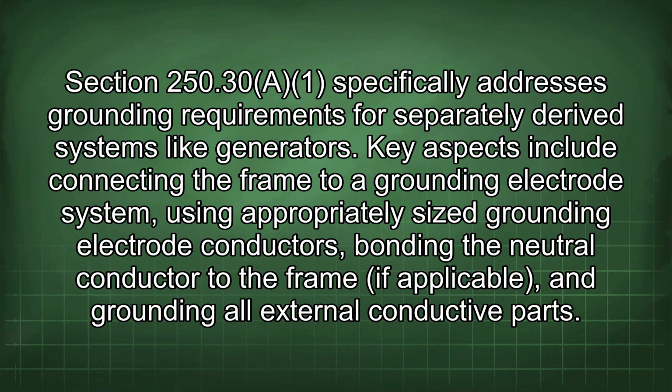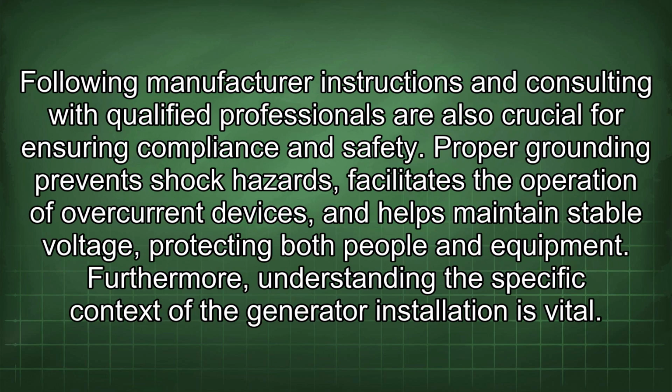Key aspects include connecting the frame to a grounding electrode system, using appropriately sized grounding electrode conductors, bonding the neutral conductor to the frame if applicable, and grounding all external conductive parts. Following manufacturer instructions and consulting with qualified professionals are also crucial for ensuring compliance and safety.